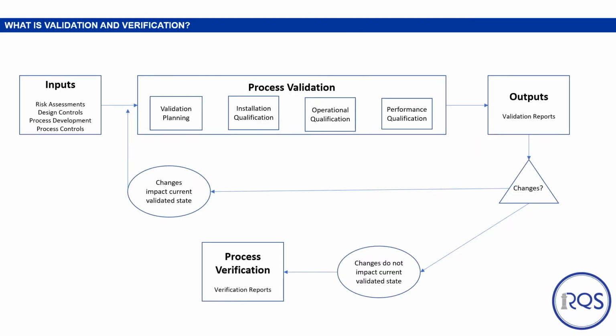So what is validation and verification? This figure shows a high-level example of the overall validation and verification process. We'll walk through each of these in more detail shortly, but we start off with our inputs, and then those inputs are taken through the validation process. Then we have outputs. As there are changes to those outputs, if they do not impact the current validated state, then simple verification can be done. If the changes do impact the current validation state, then you might have to go through the full validation process all over again. But we will walk through each of these in more detail now.